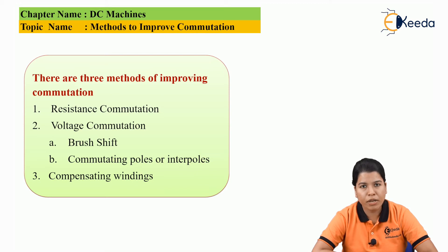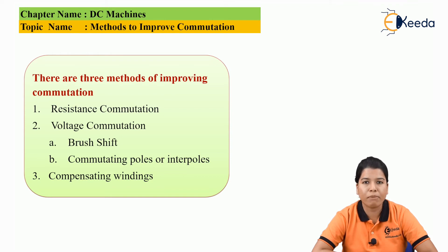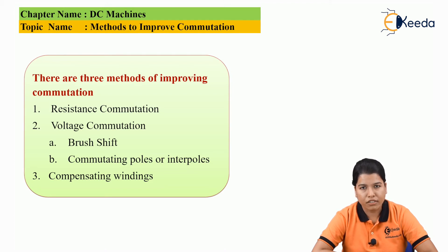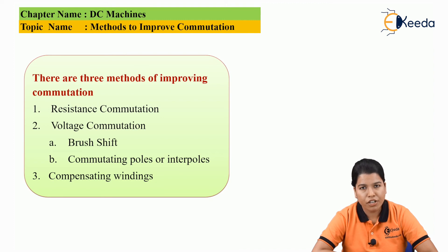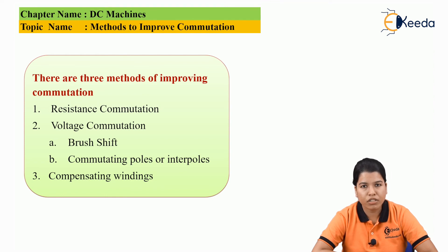The next method to improve the commutation is by using compensating windings. The compensating windings are placed inside the slots on the pole face, exactly parallel to the armature conductor, and connected in series with the armature conductor. The current in the compensating windings and the current in the armature conductor are exactly the same but of opposite polarity. Due to this, the MMF produced in the compensating winding neutralizes the MMF in the armature winding, thereby improving commutation.